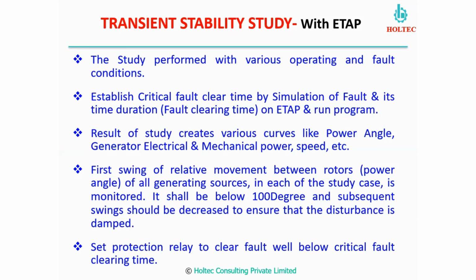for each individual power source. The method through which we can show stability is that we check the first swing, that is the power angle first swing. If it is below 100 degrees, and after that the subsequent swings decrease, that means the disturbances are getting damped, and the source will retain stable, steady state operation.